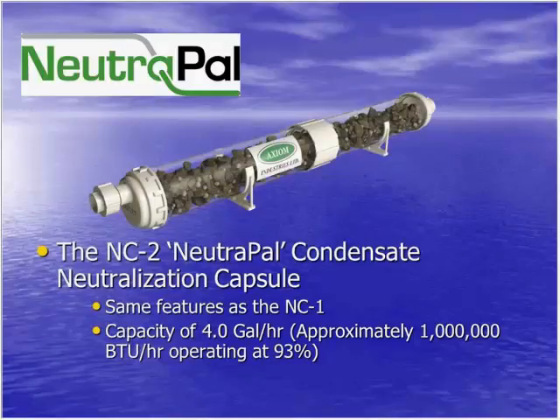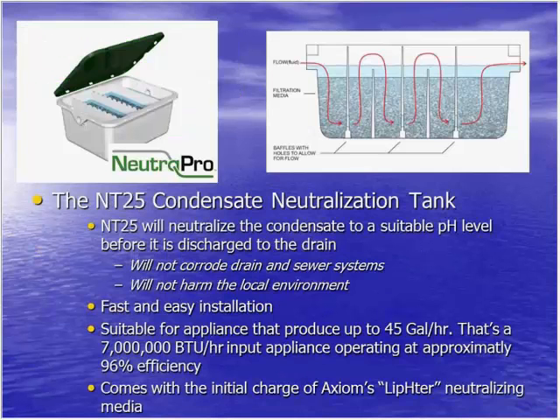This is our NT25 condensate neutralization tank. It's a low profile design with baffles, so it more effectively utilizes the volume of fluid and media in the tank by forcing the condensate through a longer flow path to make sure that the residence time, or contact time, with the media is extended as much as possible.